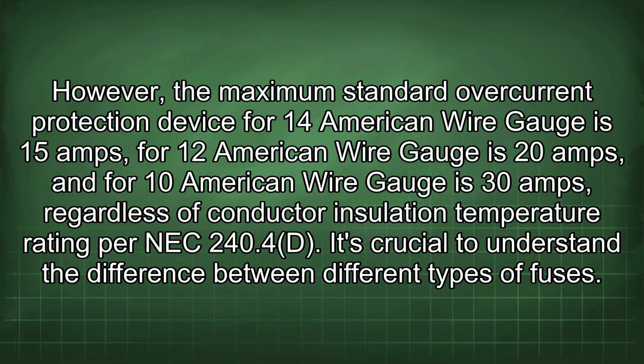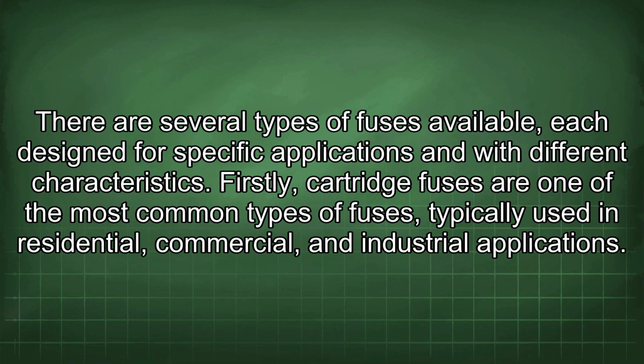However, the maximum standard overcurrent protection device for 14 American wire gauge is 15 amps, for 12 American wire gauge is 20 amps, and for 10 American wire gauge is 30 amps, regardless of conductor insulation temperature rating per NEC 240.4(D). It's crucial to understand the difference between different types of fuses. There are several types of fuses available, each designed for specific applications and with different characteristics.